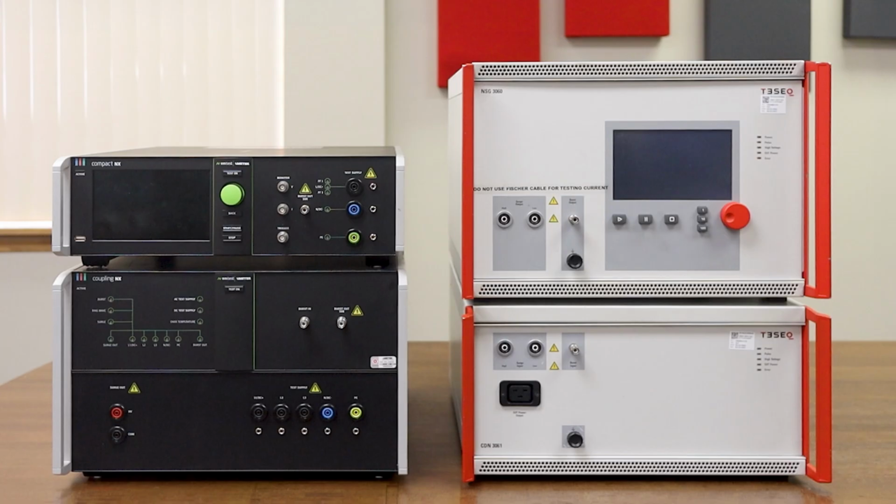Unlike some other types of immunity test equipment, transient generators and the associated coupling-decoupling networks can be fairly easily damaged. Each manufacturer has a slightly different design, and the steps in guidance in the documentation should be referenced when getting the test system set up. Let's go ahead now and get started with the first mistake we see.